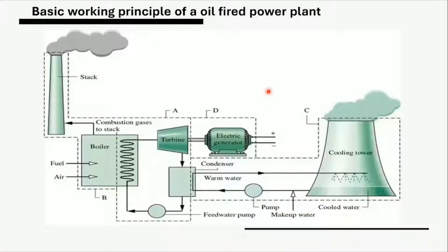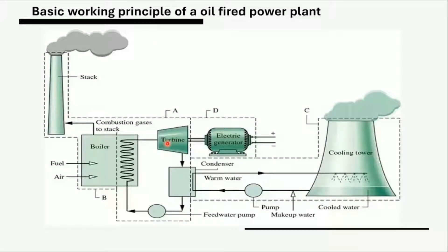In the basic operation of an oil-fired power plant, by turning the shaft of the generator we are able to generate electricity. The generator derives motion from a steam turbine, the heart of the power plant. To turn the steam turbine, you must supply high-pressure and high-temperature steam at the inlet. As the turbine absorbs energy from the high-energy fluid, its pressure and temperature drop toward the outlet. High-capacity power plants often use different stages of steam turbines, such as high-pressure, intermediate-pressure, and low-pressure turbines. If we can bring the low-pressure and low-temperature steam back to its original state, we can repeat the process.